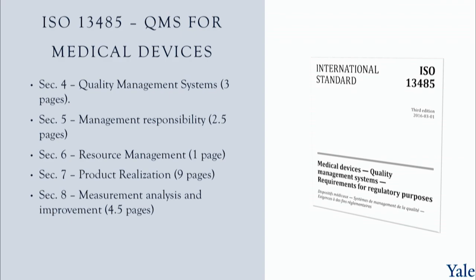The medical device standard for quality management is ISO 13485, and you can actually see the core sections here. Again, of course, the focus is on product realization, but all the other components are there. And if you look at 13485, it will get into details that are medical specific. Things like sterilization will come into this description. We are not going to go through this standard directly. This is about the last time we'll mention it explicitly.